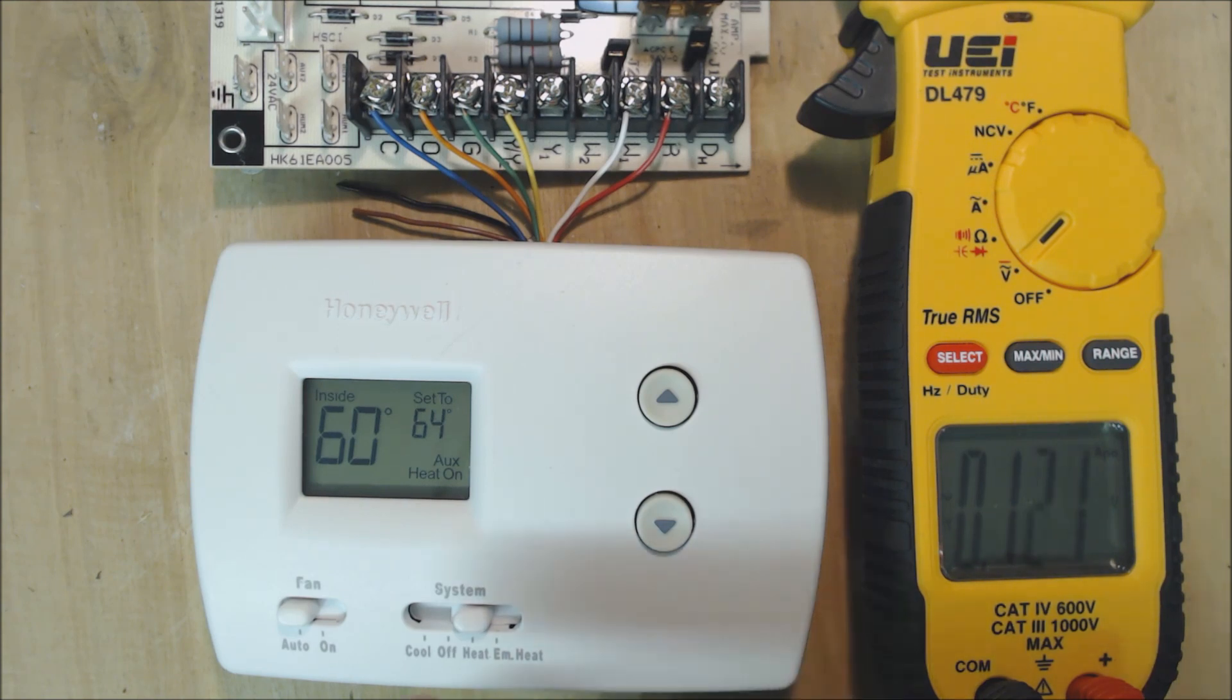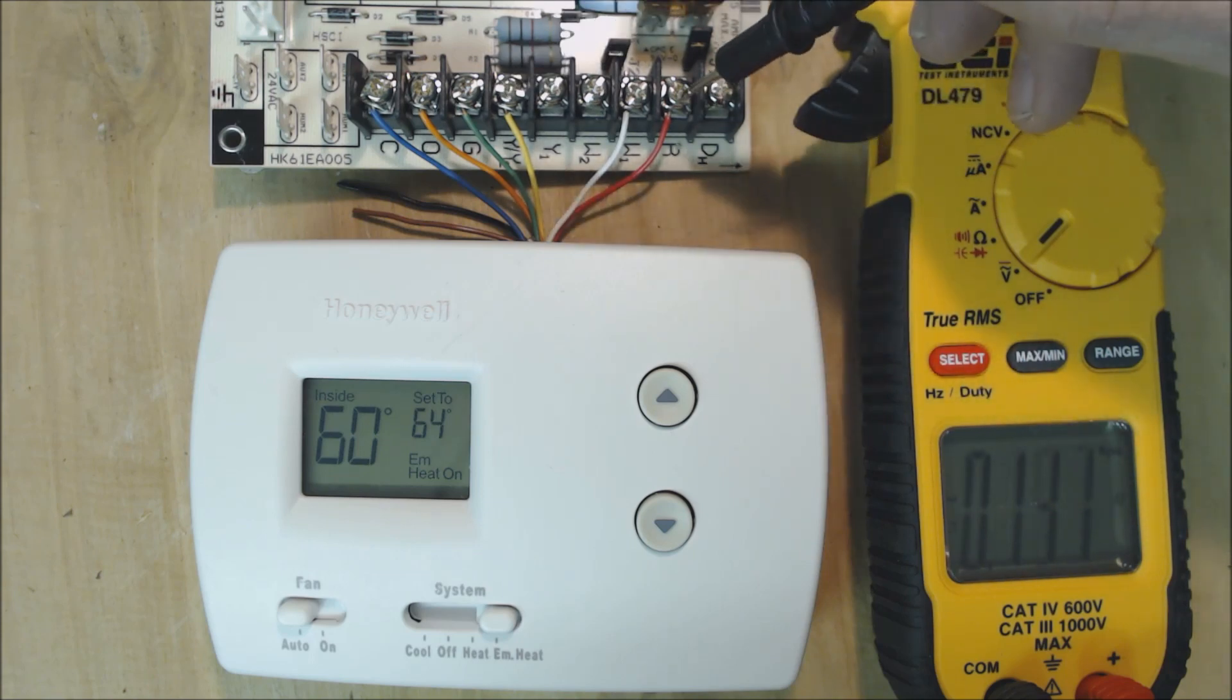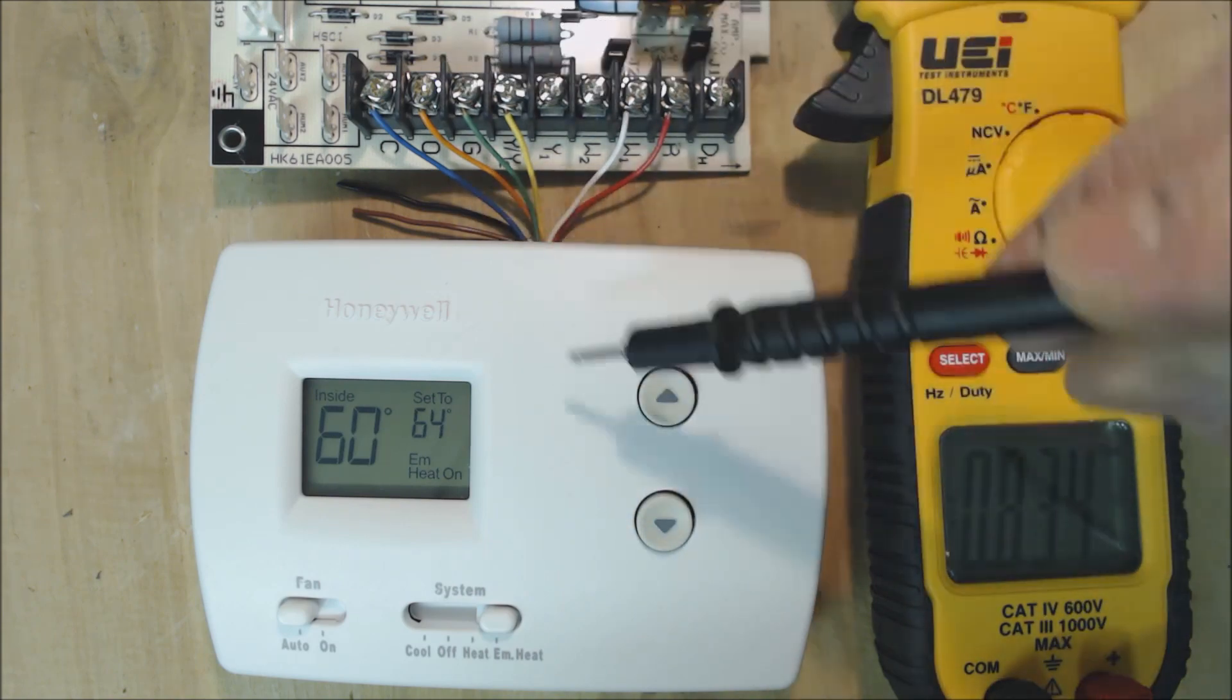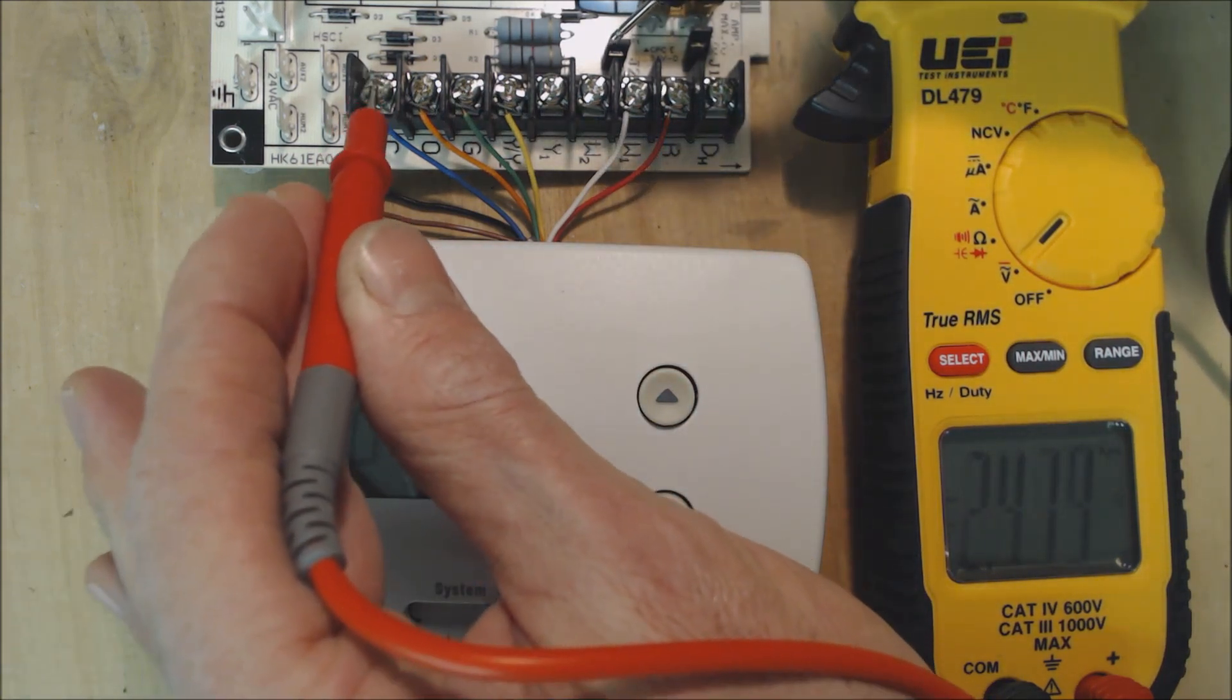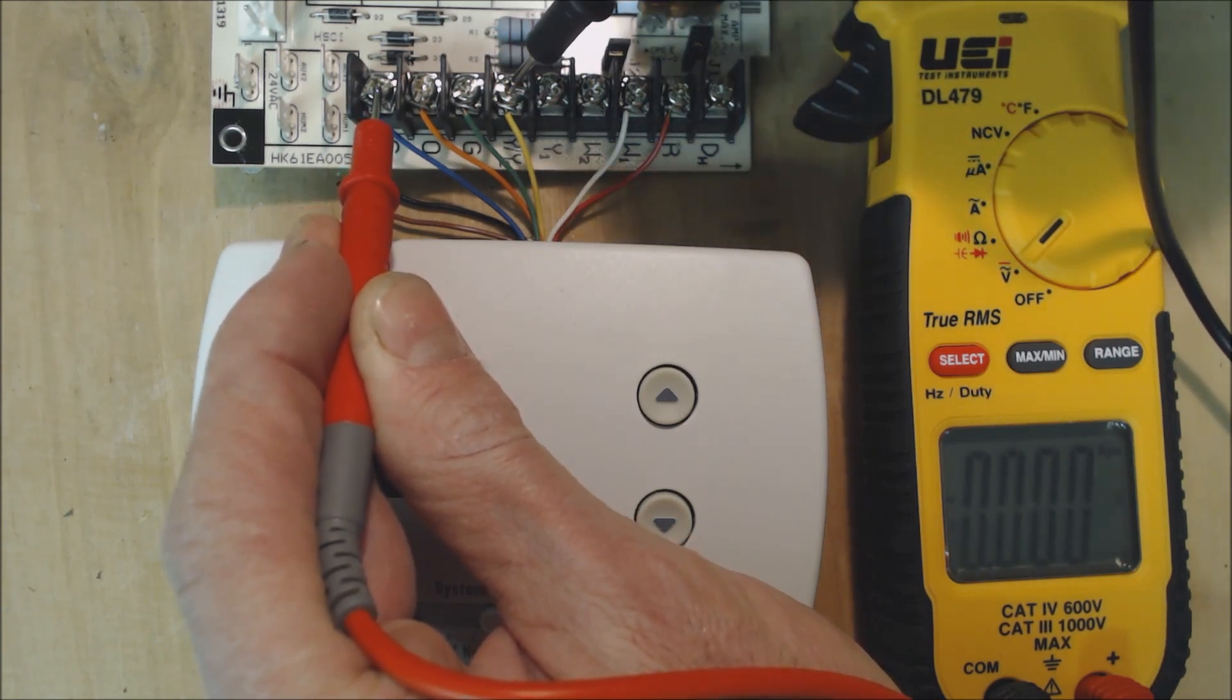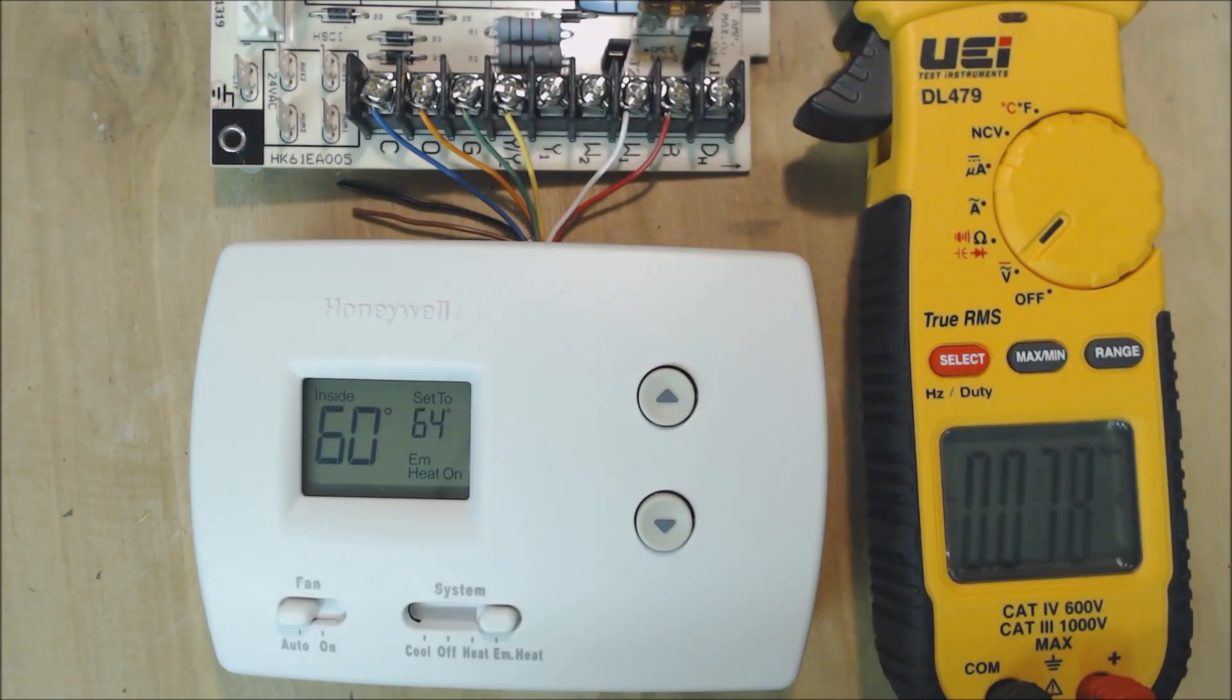Now we're going to turn on emergency heat. Now we should not have any power connecting to Y. Basically all that's happening now is R is coming into the thermostat, it's touching W and G, and it's coming back to G and W over here. We've got 28 volts there. We should not have any voltage on the Y because the compressor should not be running now, and we should have 28 volts once again on the G.